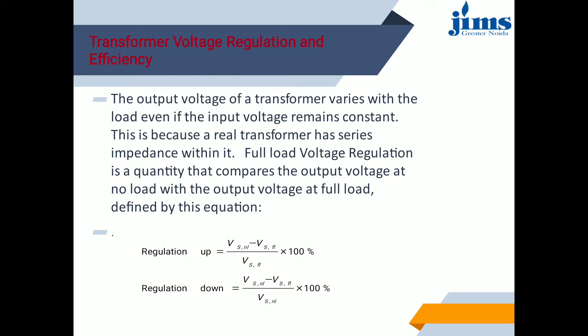The way in which the secondary terminal voltage varies with the load depends upon load current, the internal impedance, and the load power factor. The change in secondary terminal voltage from no load to full load, with primary voltage and frequency held constant, is termed the inherent regulation. The output voltage of a transformer varies with the load even if the input voltage remains constant, because a real transformer has series impedance within it. Full load voltage regulation is a quantity that compares the output voltage at no load with the output voltage at full load.